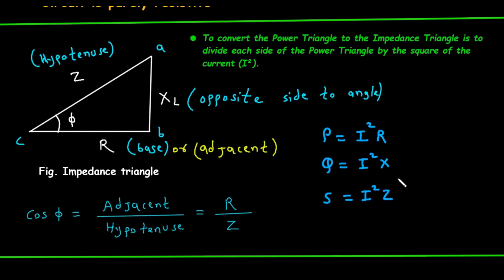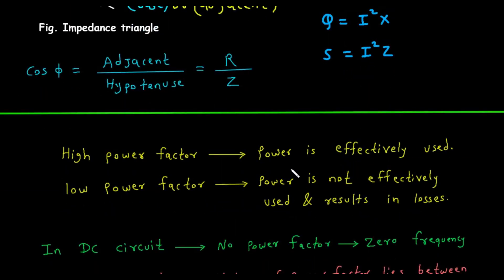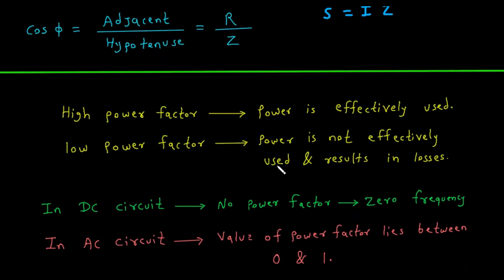So, why is all of this important? The value of the power factor has significant practical implications. A high power factor, meaning a value close to 1, indicates that power is being used effectively — most of the power being supplied to the circuit is being converted into useful work. On the other hand, a low power factor, meaning a value much less than 1, indicates that power is not being used effectively. A significant portion of the power is reactive power, which sloshes back and forth in the circuit without doing any real work. This leads to higher overall current, which in turn results in greater energy losses in the system, primarily as heat.